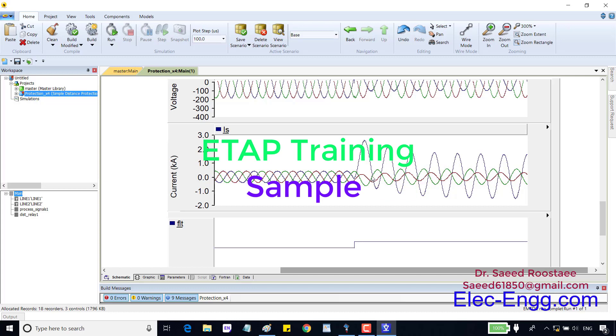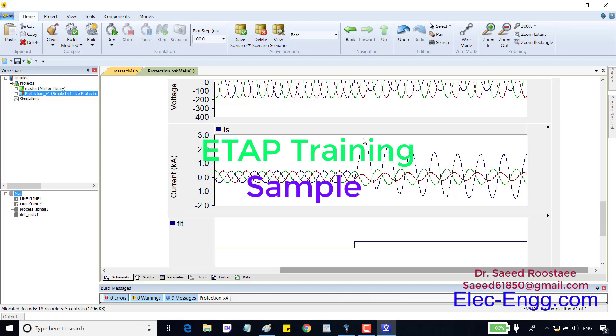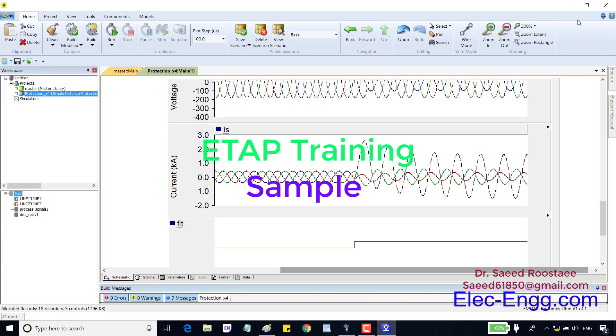1.5 cycles to 4 cycles is also a very important period and protection relays should open the circuit breaker at this period. This period is called transient time. After 4 cycles the DC element in the short circuit current is almost zero and we have an AC current only. In this time we can find minimum fault current. This time is called steady state. There are different methods and standards to model the short circuit current and now we are going to check the parameters of these methods.